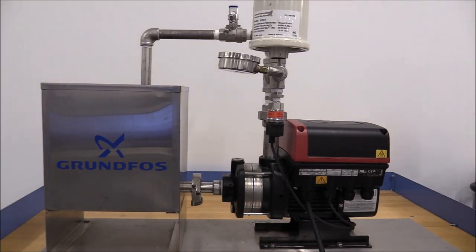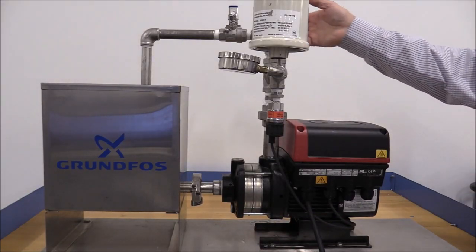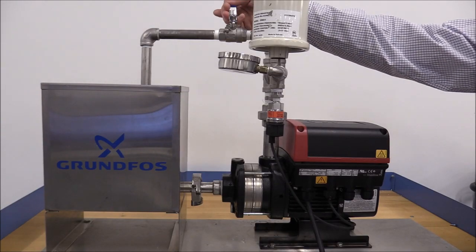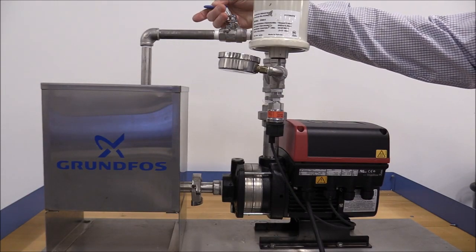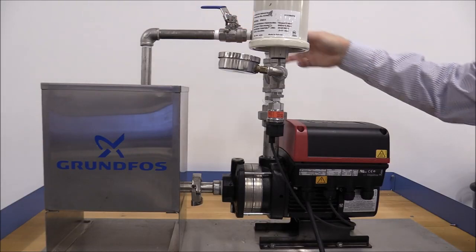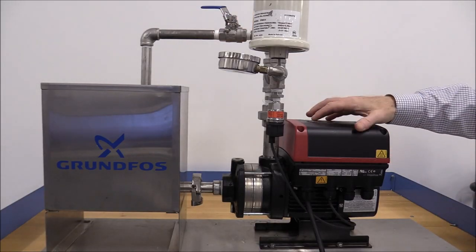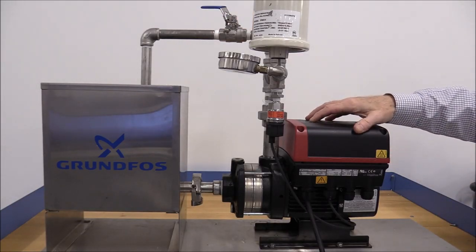I'm going to go ahead and put power to the pump. Then I'm going to slightly open the discharge valve, because you never want to start a centrifugal pump against a closed valve. Then I'll press the on-off button to start the pump.